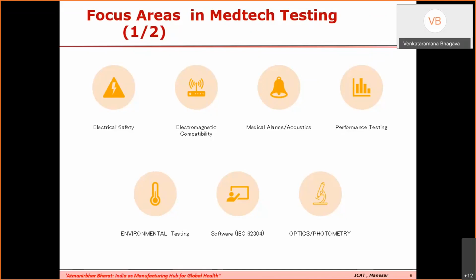So for example, since I am just quoting about ventilators, if you look at ventilators, there are about 5 or 6 or 7 types of ventilators from a regulatory point of view. For critical care ventilators, the requirements are the most stringent, and the standard is ISO 80601-2-12. The next level is the ventilator in the anesthesia machine or the anesthesia workstation, which is the -2-13 standard. The next category would be something like a transport ventilator, which is again -2-84.